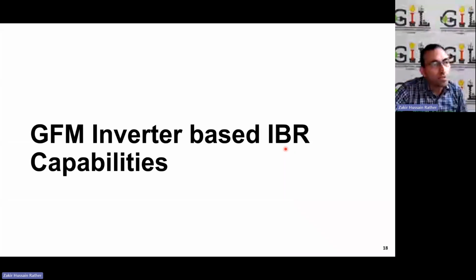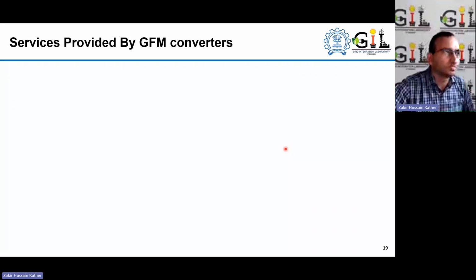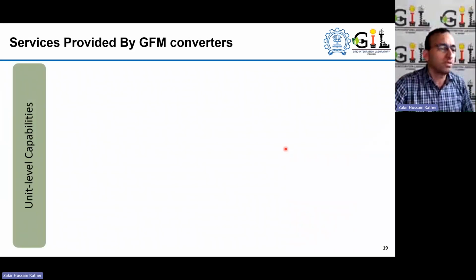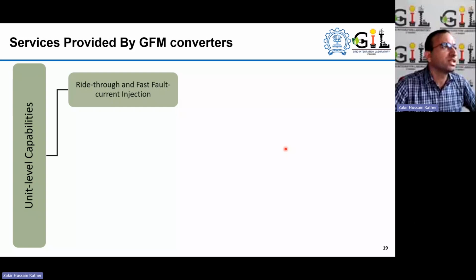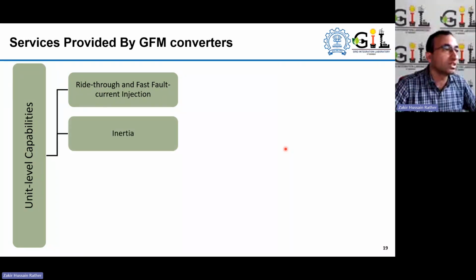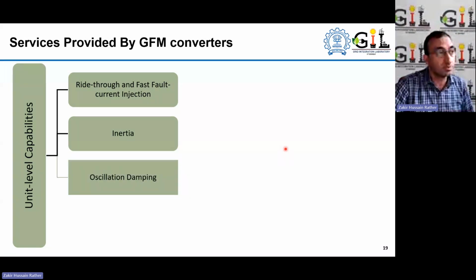Now, looking at the capabilities of these IBRs which use grid forming technology, if you look at what they can provide at unit level, by unit level I mean inverter level for solar PV and WTG level for wind turbine generators. They do have better ride through and fast fault current injection. They can provide that inherent inertia that I was mentioning earlier. They can provide damping of oscillation.